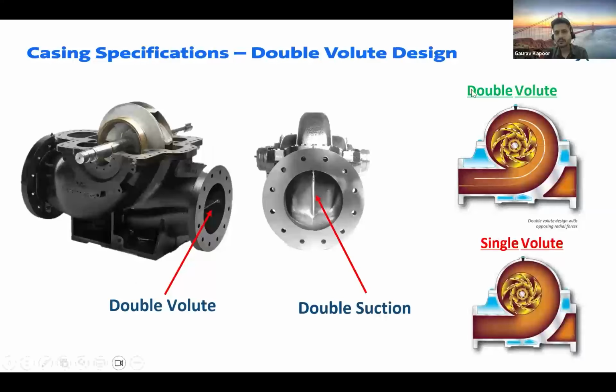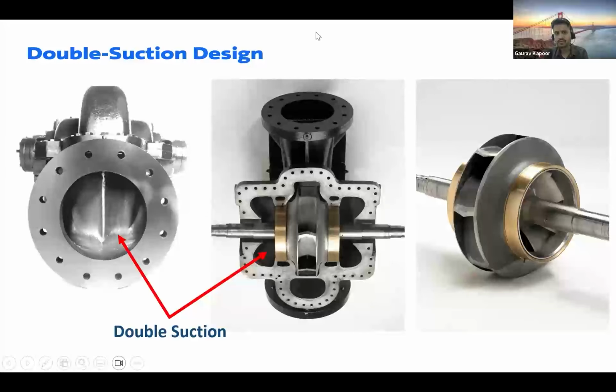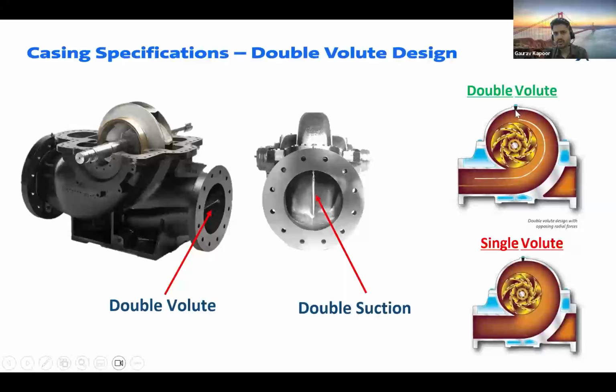Now the other point which we need to always remember is double volute. This was double suction, and this is double volute. Double volute, if you see, there is a small casted metal wall within the casing itself. So this thin line, if you see, it's a metal casting, and what it does is make sure that when the water is exiting the casing through the discharge flange, it also exits in equal proportions. So this is double suction, where you have a hull shape structure, and if you see a straight line here, that's double volute. This is suction, this is discharge. This is where the water goes in, and this is where the water comes out.